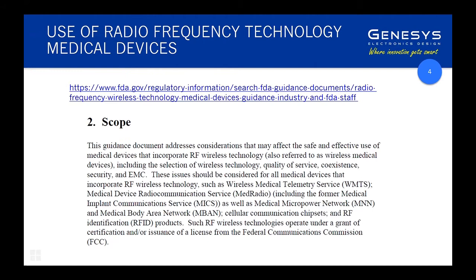To use Bluetooth or Wi-Fi in those environments — people are doing so — but be aware that you need to be very careful about the risks in sensitive environments. Why is Bluetooth and Wi-Fi okay but not 4G? Mainly because the radiated power levels are quite low — tens of milliwatts versus watts of peak transmitted power for a 4G transmitter. Radio waves can induce electrical signals in conductors — for example, if you use a cell phone right next to a catheter going into a patient's heart, you could generate electrical signals that disturb heart function.